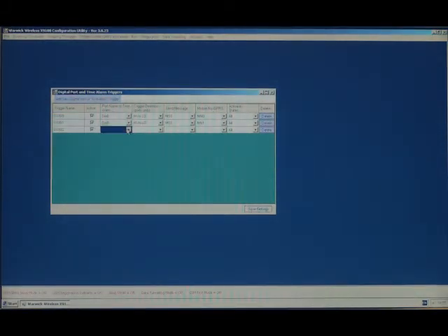And to repeat the operation so it sends the message open, we go to digital port and time alarm triggers, add new digital port time alarm trigger. It's going to be D in 0. This time the direction's low to high. We're going to send message MS0 to MN0. Add a new trigger, which will be D in 0, low to high. Message is MS0 to MN1, the second mobile phone.